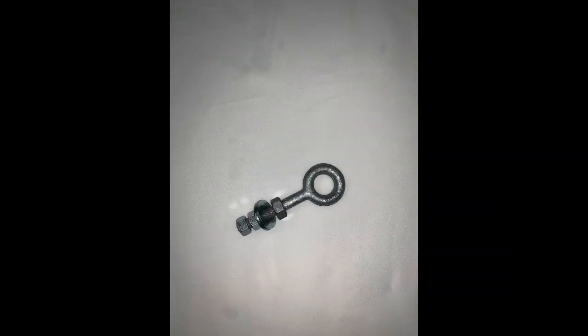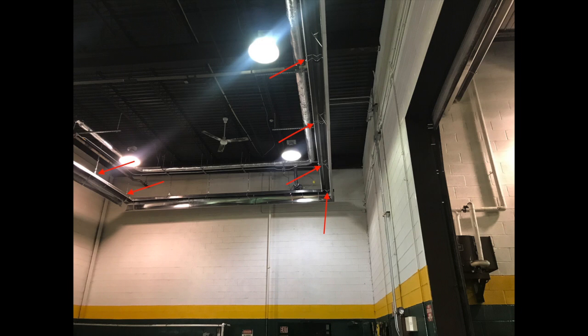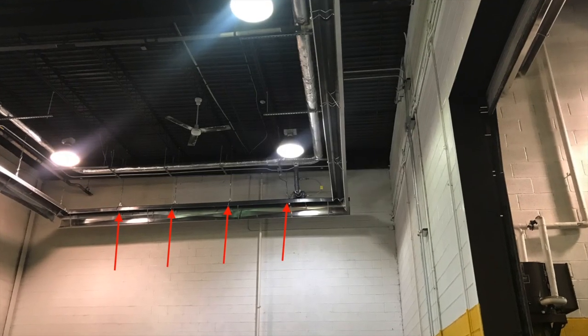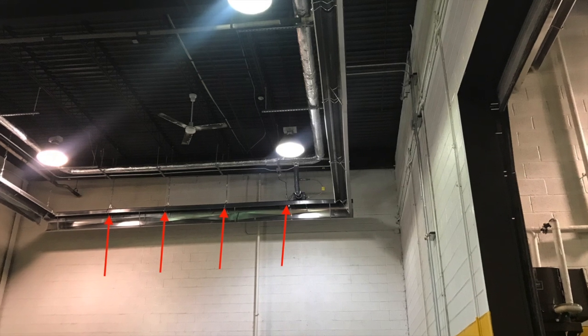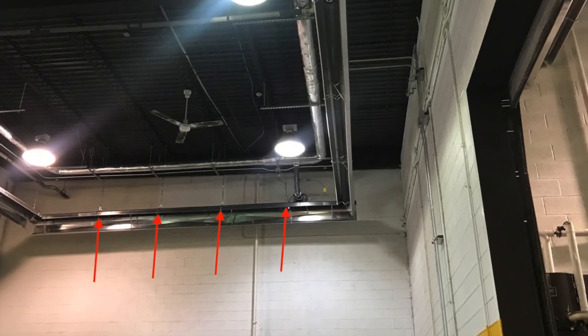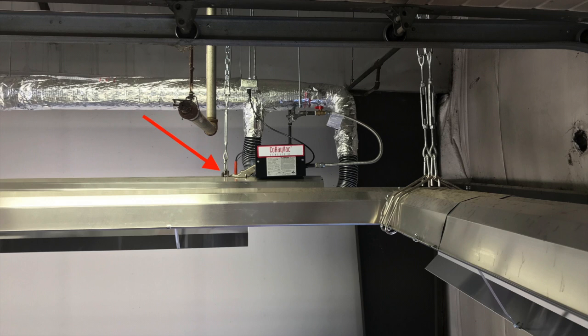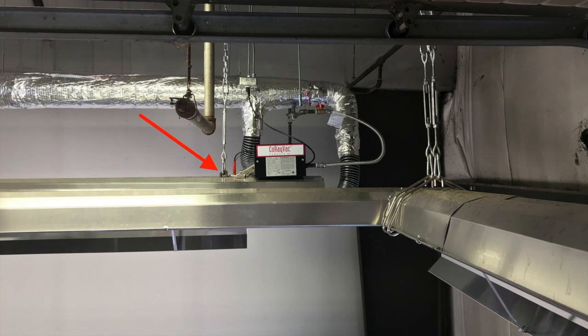Each 3/8 eye bolt is supplied along with 3 nuts and 2 washers. This is to ensure that 2 nuts on top and 1 below the purlin are installed on each 3/8 eye bolt to suspend the Schedule 40 pipe. Hangers have a maximum spacing of 7 feet, which can be hung when going with the purlins at 7-foot intervals. Hanging the pipe perpendicular to the purlins is usually every 5 to 5.5 feet, as that is the normal spacing of the purlins.